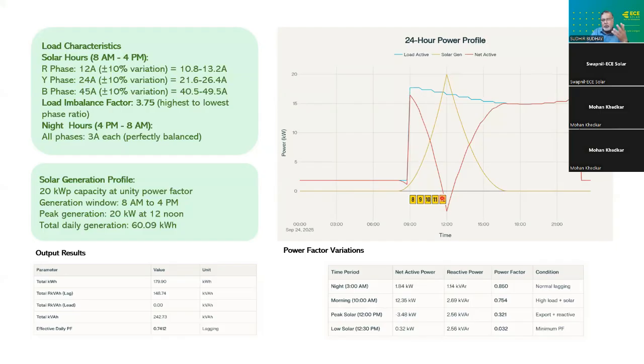It starts exporting power to grid till 12:30 or whatever, depending on your capacity and size and location of your installation. And again, the demand on grid will start increasing. So this is precisely what I was trying to draw your attention to.